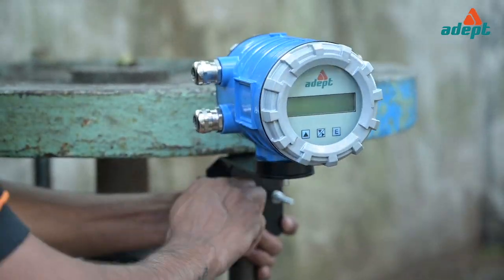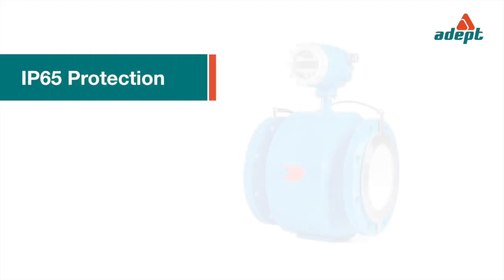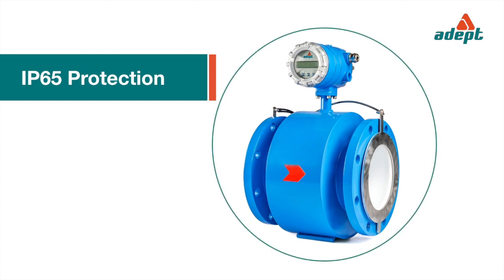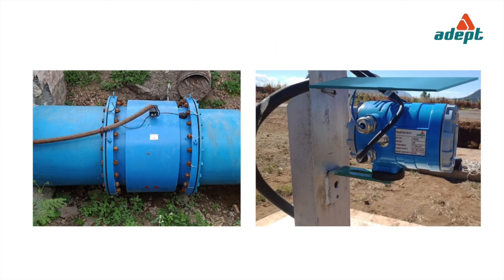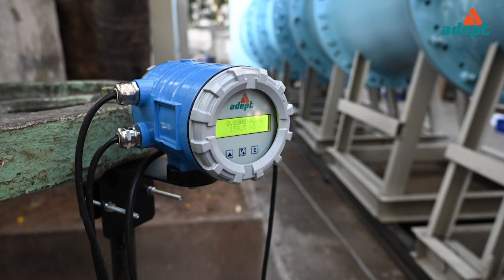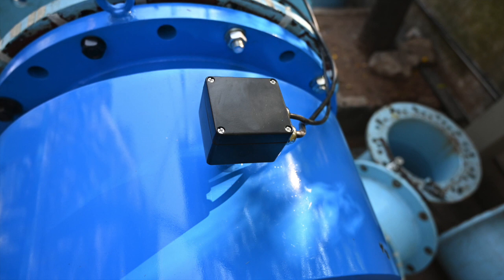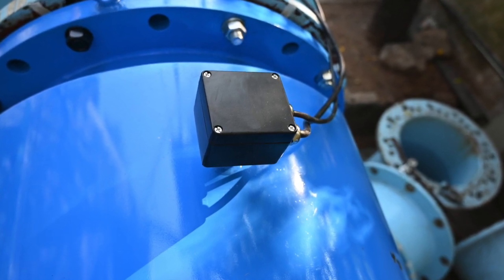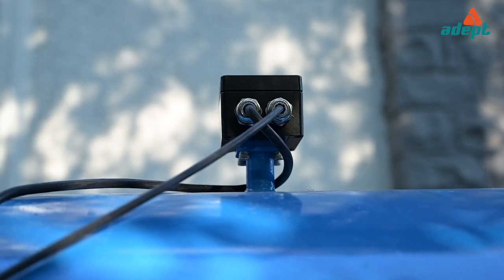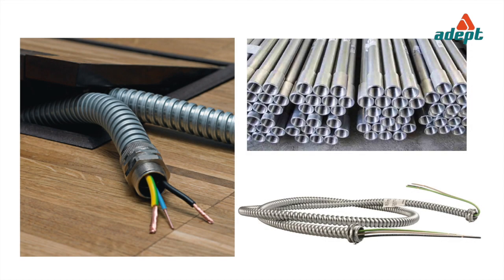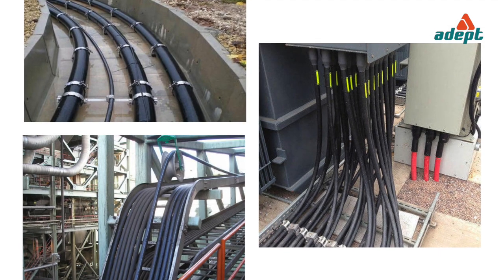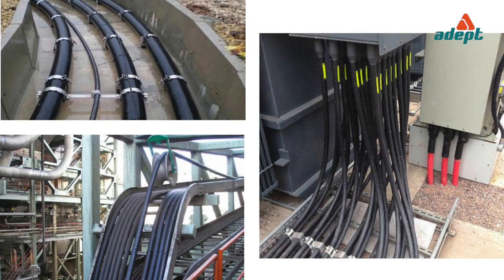The integral transmitter has IP65 protection and should be installed above ground in a secured location. In the case of underground installation, the flow meter should have a remote type transmitter. The signal and coil cables connecting the transmitter and flow tube are sensitive to electrical noise. It should be ensured that such cables are passed through metal conduits which are separated from the conduits carrying HT and LT power cables.